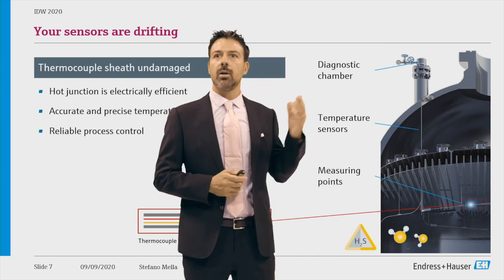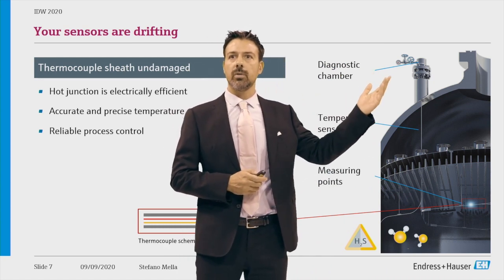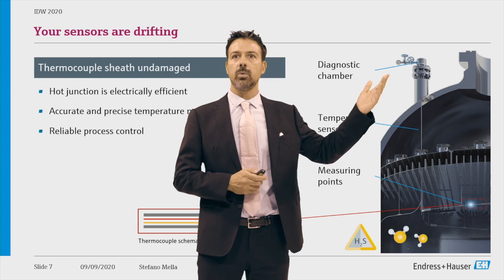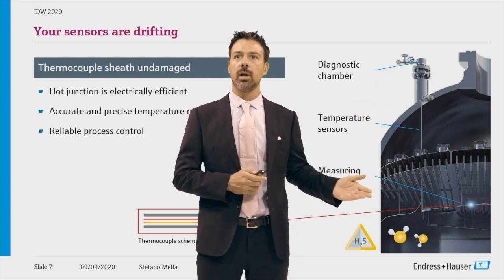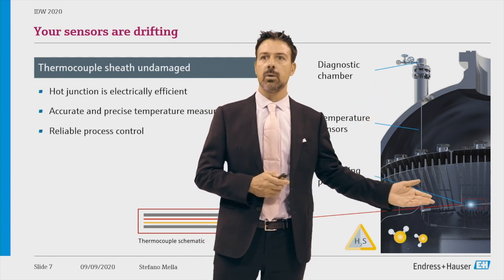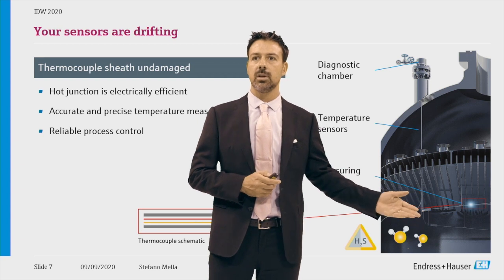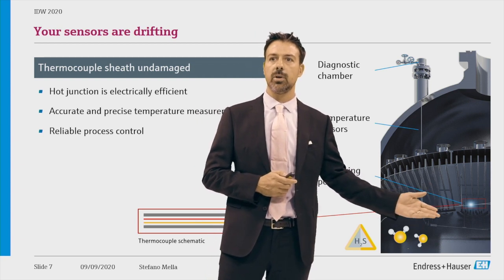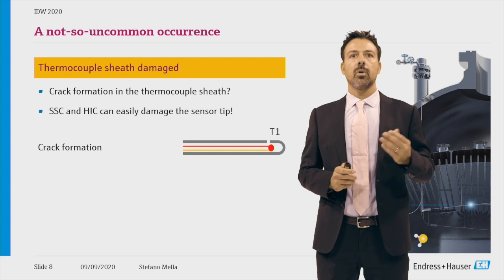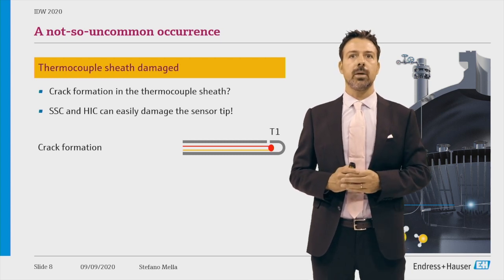This is a typical installation. From the top, we have the complete thermometer provided with its own diagnostic chamber, and going down here, we see the routing of the sensors and some measuring points. What happens when a thermocouple sheath gets damaged?